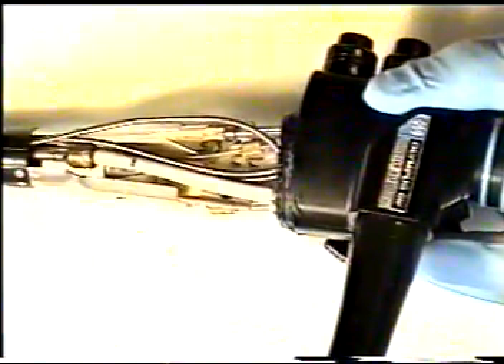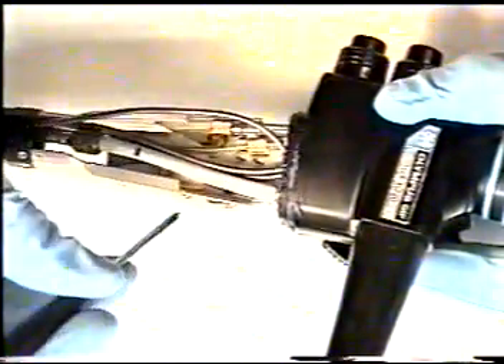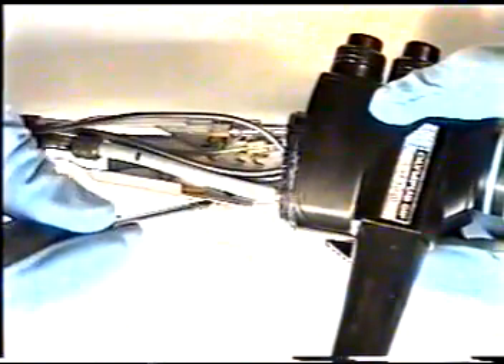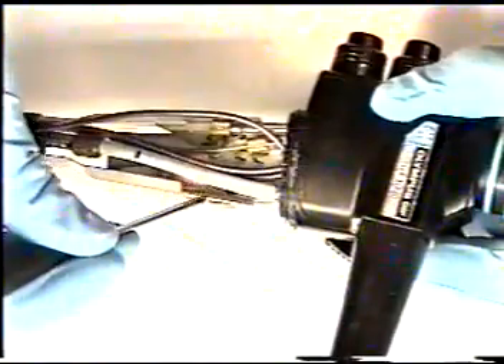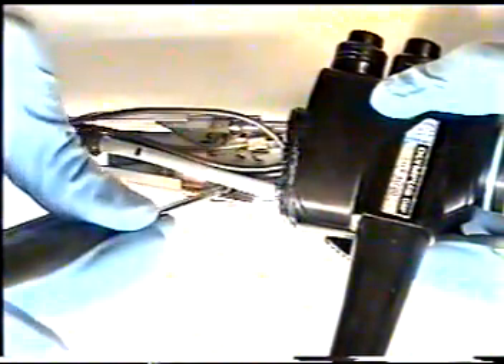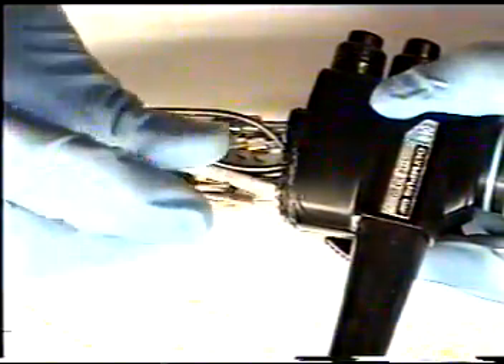Using Phillips screwdriver and small Phillips screws, tighten down block into body. Turn over the instrument. Inserting the other two screws into block assembly. Again, this is very critical as not to damage any of the light bundles or suction channel. Take screw and gently push, in this case suction channel side, screwing block into body.